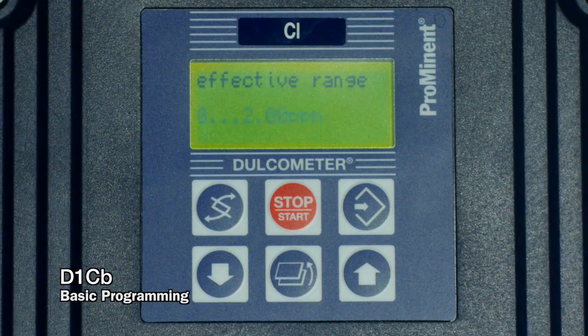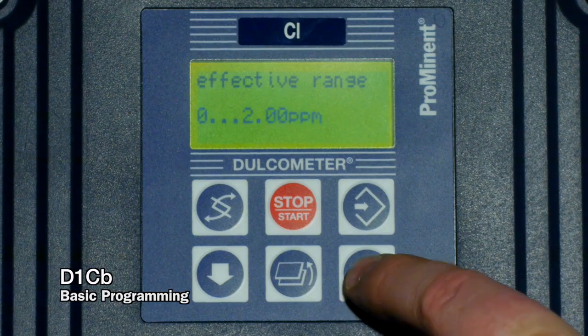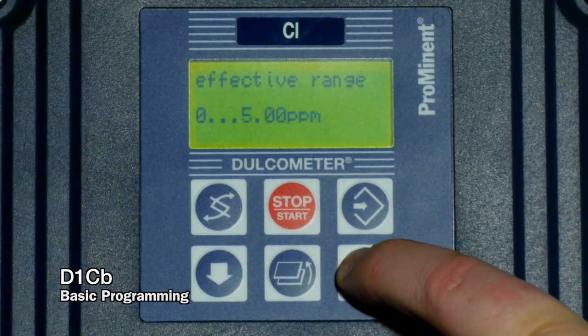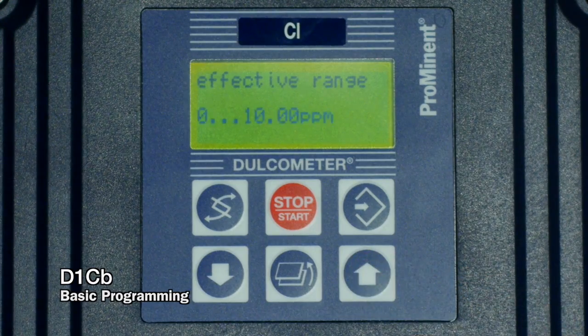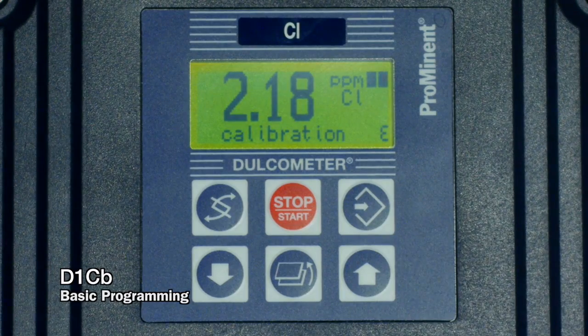Now it's going to ask us the range of the sensor, and you'll find that information right on the label that's on towards the top of the sensor. So if we scroll with the up or down arrow button to match what that information is, let's say it's a 0 to 10 ppm sensor. With the enter button again to confirm that, you see the unit goes back to our main screen.